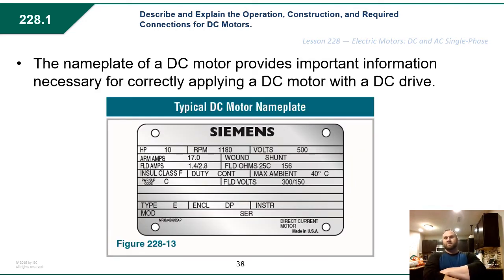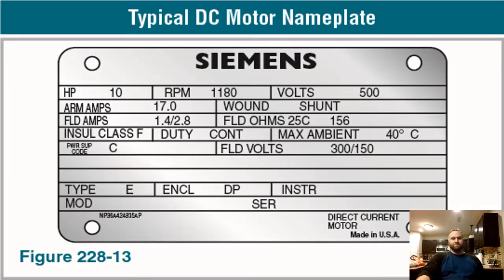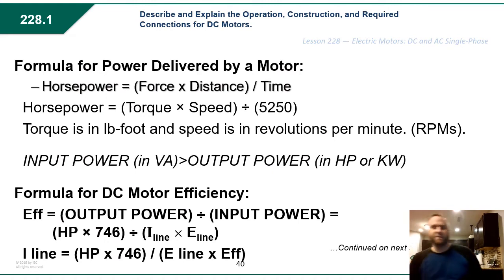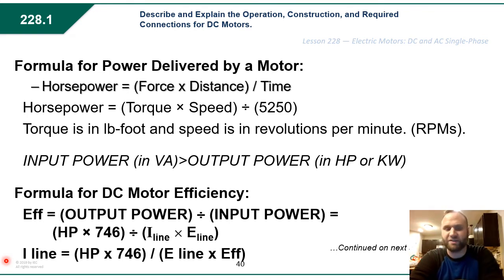The nameplate on DC motors provides important information necessary for correctly applying the motor with a DC drive. When doing an install, check the nameplate: what horsepower is it, how many volts does it take, what type of wound motor is it — shunt, series, or compound — and what's its overall rating. The efficiency formula is output power divided by input power — I might ask about that on the quiz. Horsepower equals torque times speed, or force times distance divided by time. Horsepower times 746 gives you watts: a 10 HP motor equals approximately 7,460 watts.